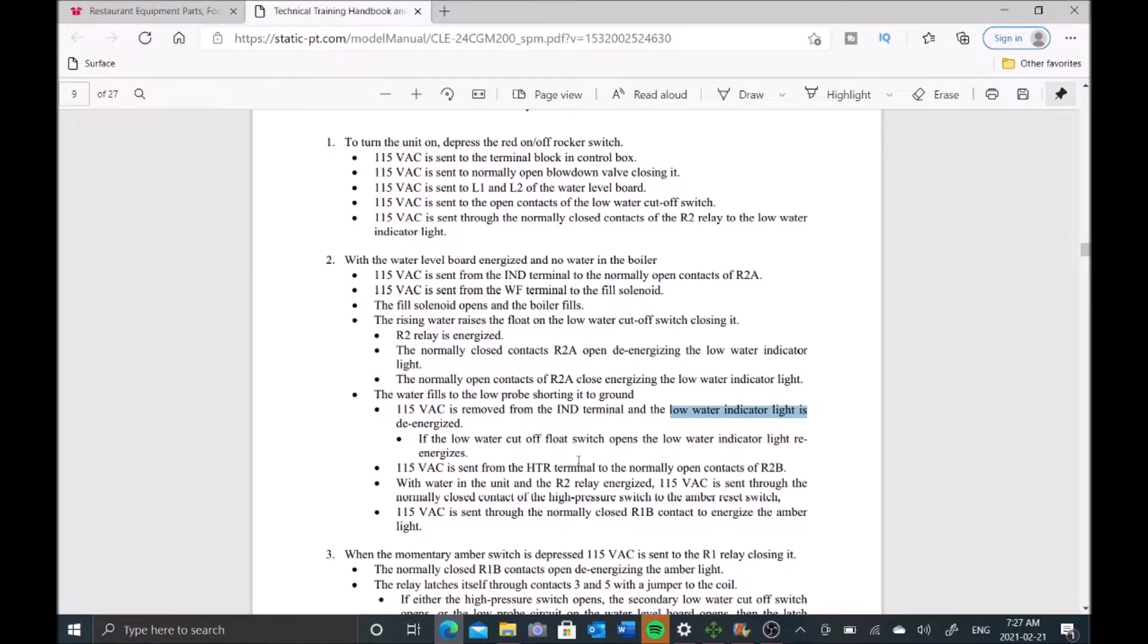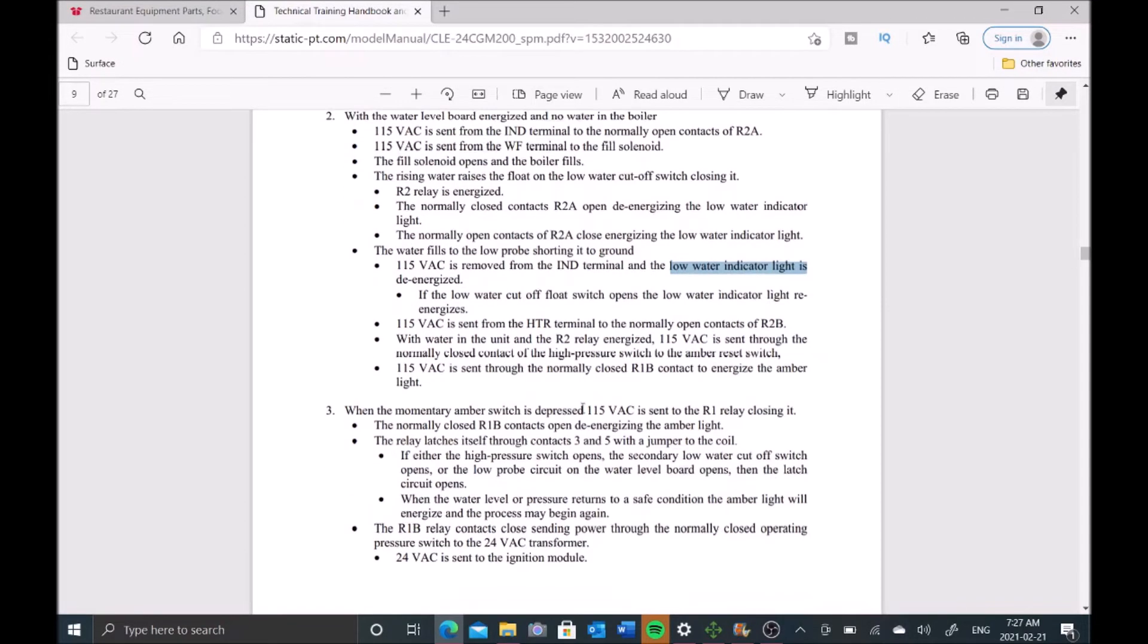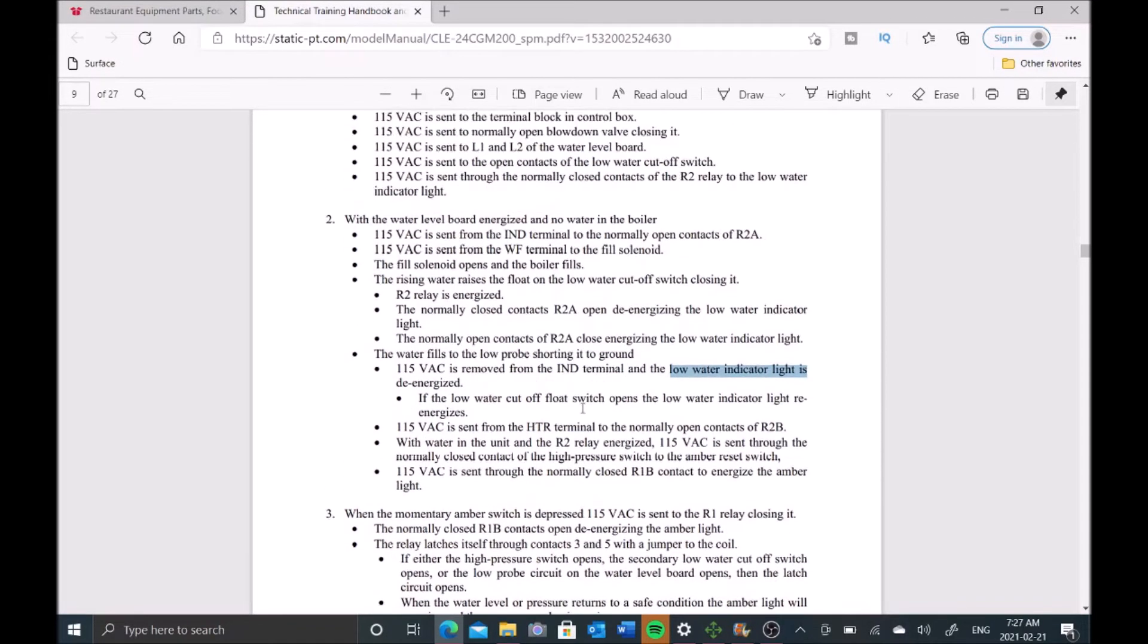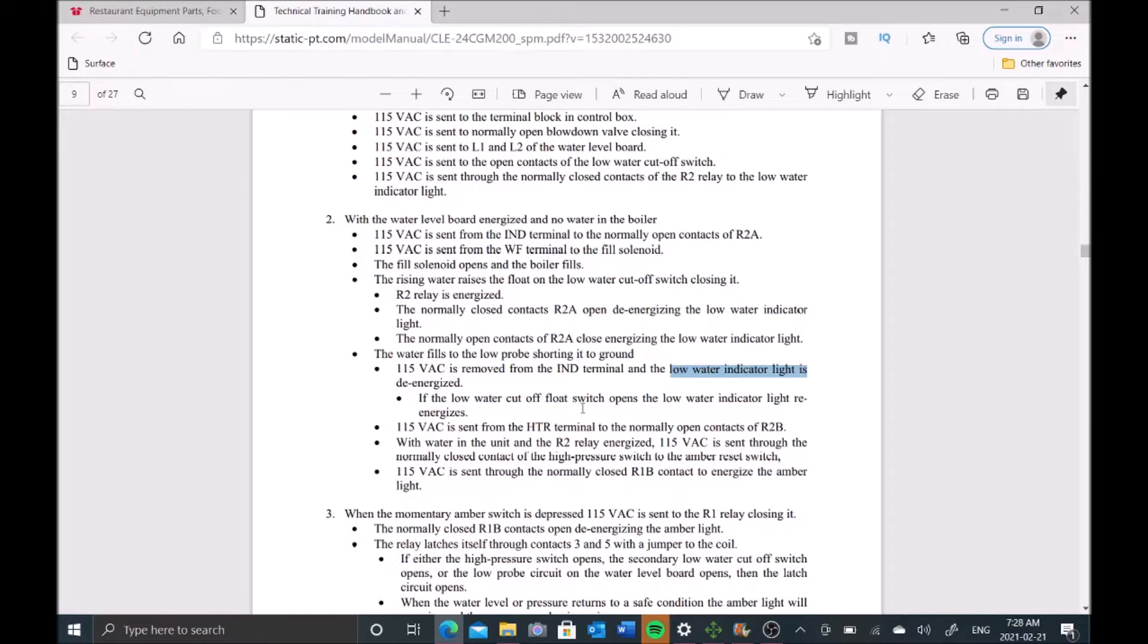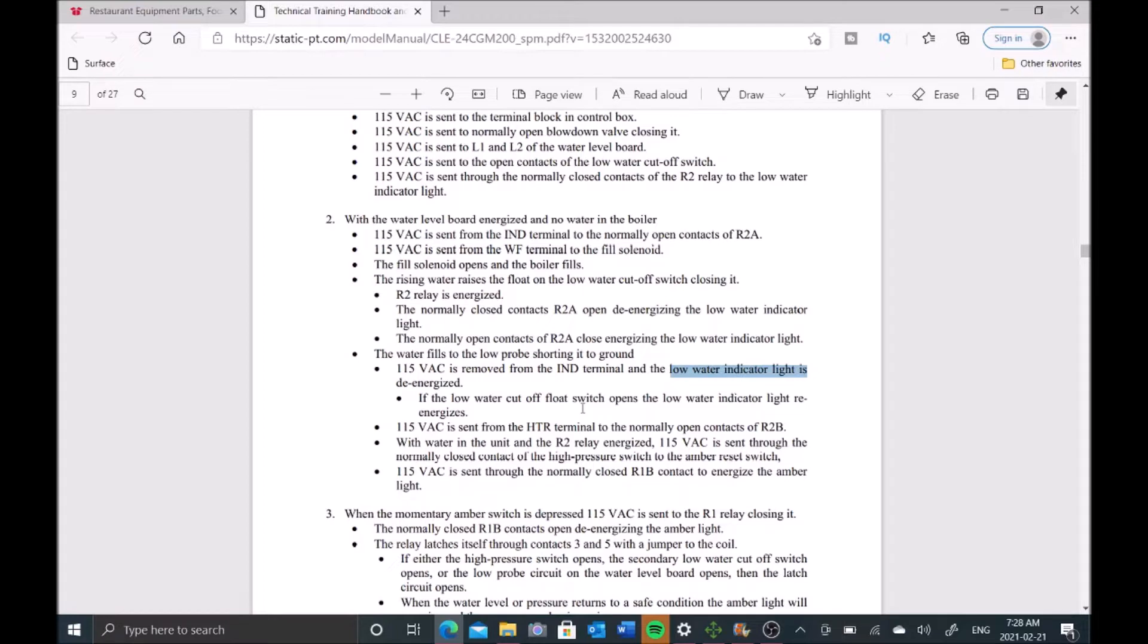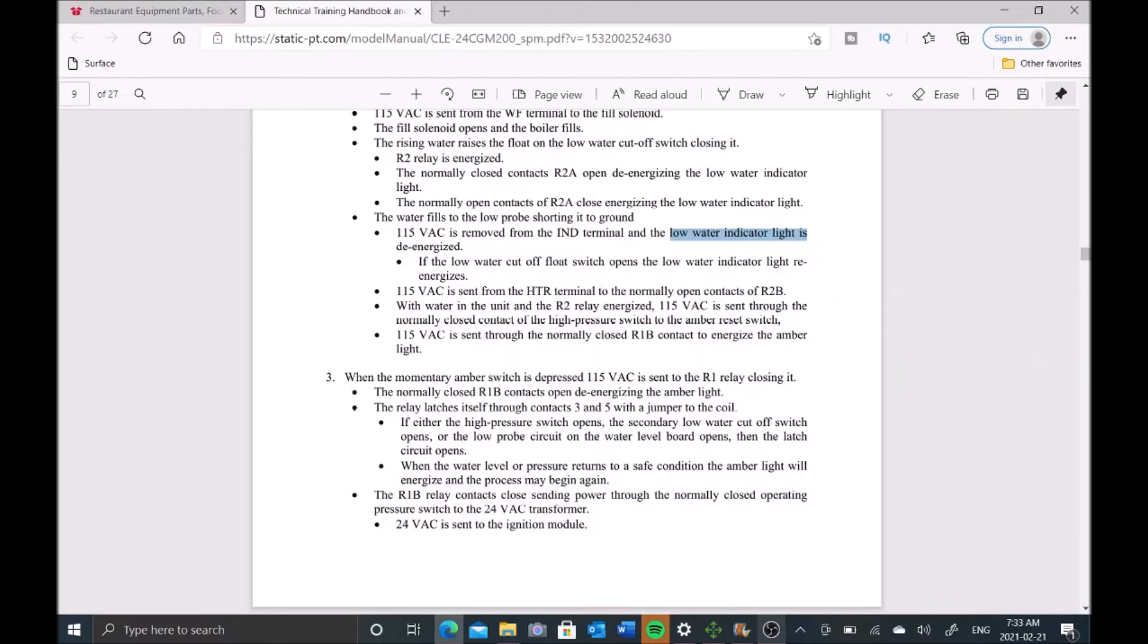Finally we have a third probe, which is the high water probe. Its purpose is to tell the solenoid when to close so we don't keep filling the boiler. In this case, we know the high probe's working because the solenoid has closed and we're no longer filling the boiler. That leads me to believe the issue is either with the low probe or with the secondary low water cutoff.